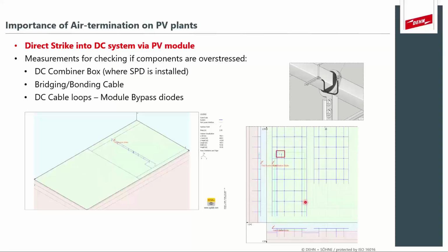When they are separated far apart, we will see the induced effect that we saw in the lab testing. We want to see what current and voltage is generated within these DC strings, to see if that will also cause subsequent damage to the PV modules and whatever electronic equipment is installed inside that combiner box.